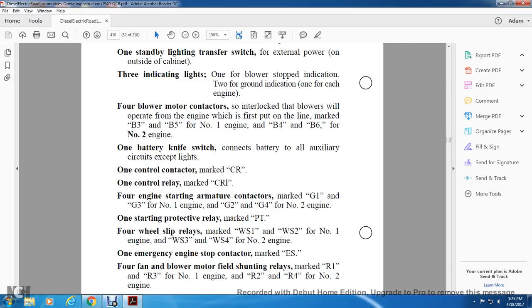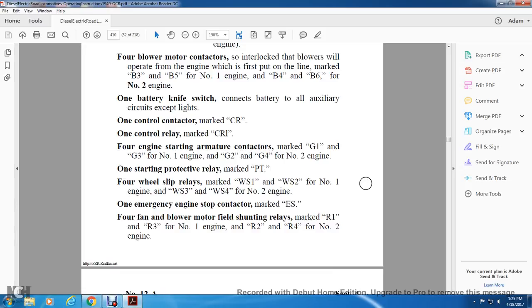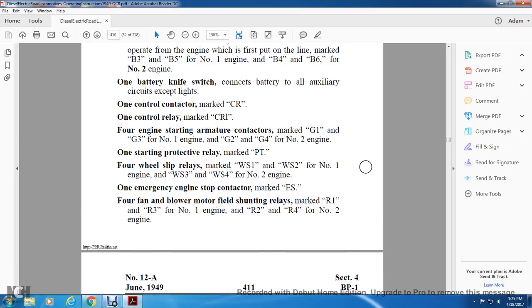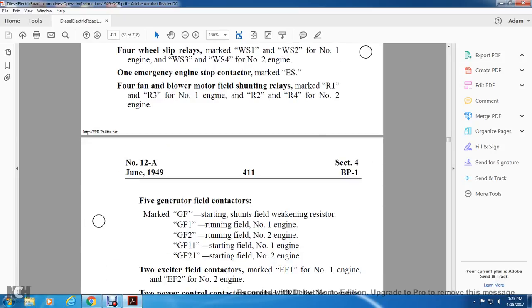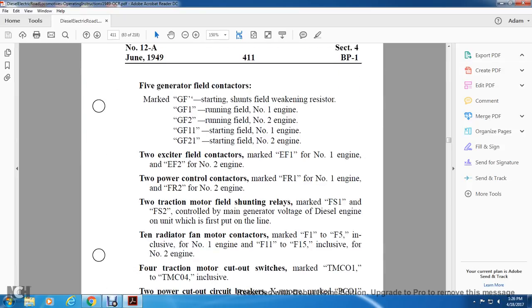The slip relays are WS1 and WS2 for the number 1 engine, WS3 and WS4 for the number 2 engine. An emergency engine stop contactor is marked ES. Four fan blower motor field shunting relays are marked R1 and R3 for the number 1 engine, R2 and R4 for the number 2 engine. Generator field contactors are marked GF, with the starting shunt and field weakening resistor GF1 for the number 1 engine and GF2 for the number 2 engine. Two exciter field contactors are marked EF1 for the number 1 engine and EF2 for the number 2 engine. Two power contactors are FR1 for the number 1 engine and FR2 for the number 2 engine.